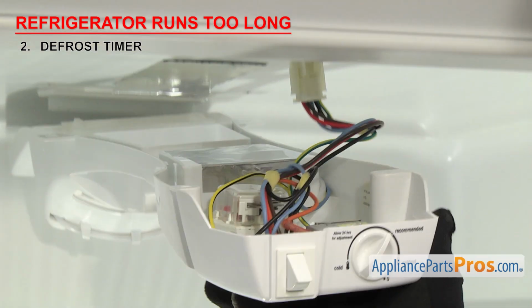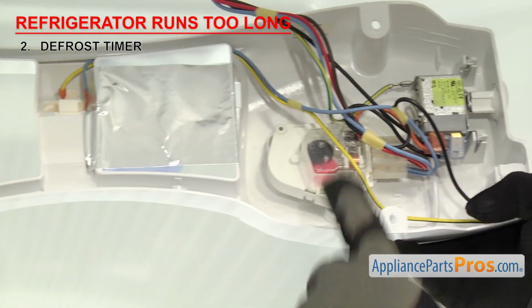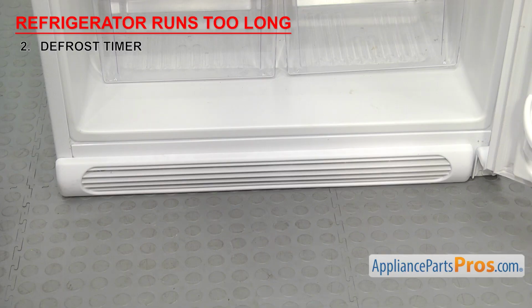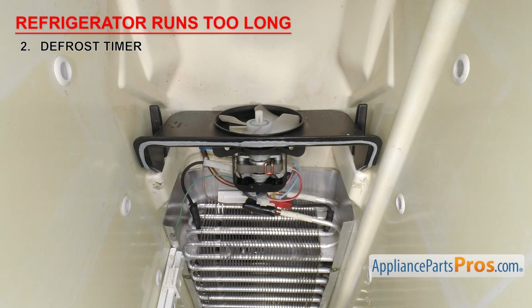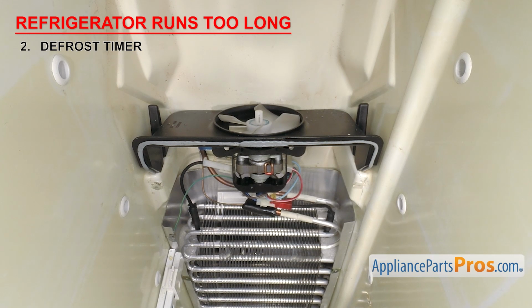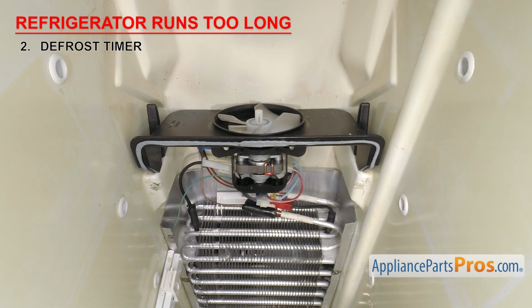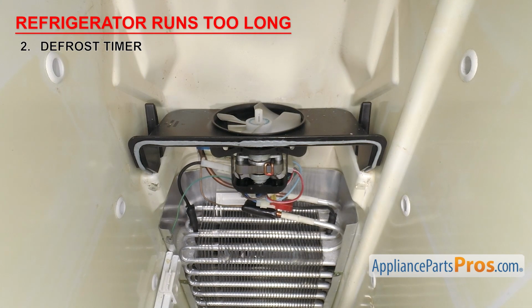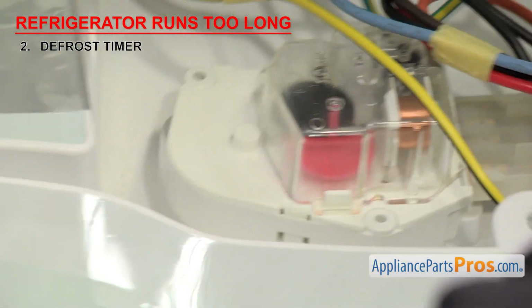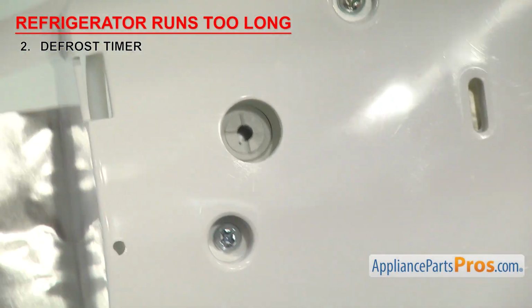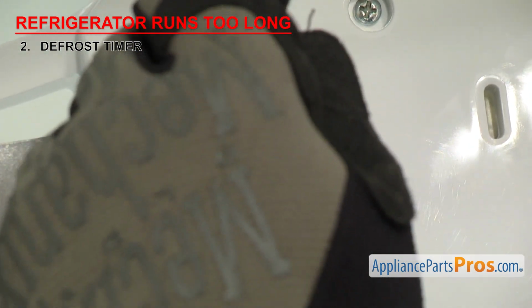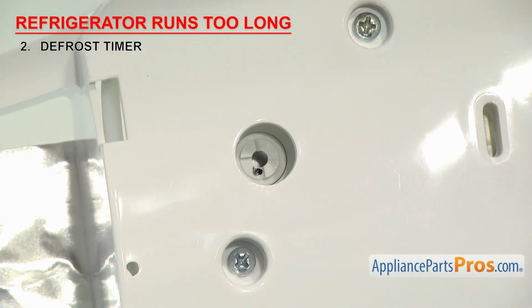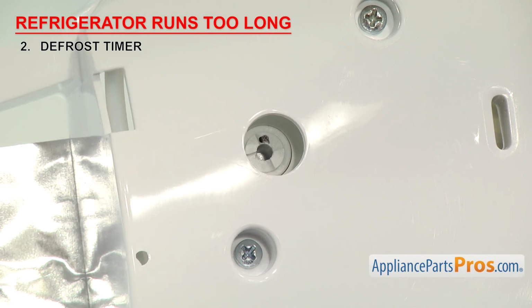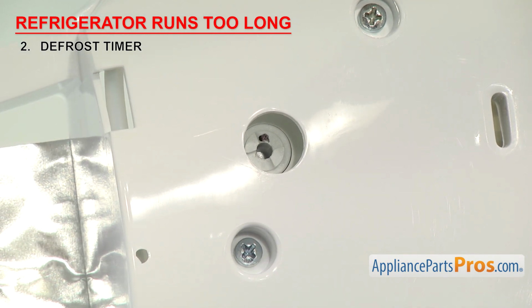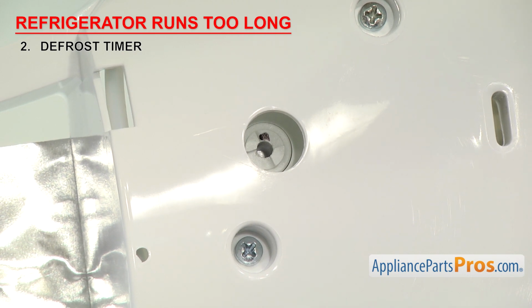Defrost timers are usually mounted in the control section of the refrigerator, but on older models, they may be behind the kick panel. If your refrigerator runs too long, it could be that the defrost timer has failed. When this happens, the evaporator freezes up, cold air can't be circulated around the unit, and it has to run longer to try and bring the temperature down. In order to check and see if the timer motor is advancing, you can mark the shaft of the timer and then check later to see if it's moved. If it didn't, then the motor or gears have failed and the defrost timer will have to be replaced.